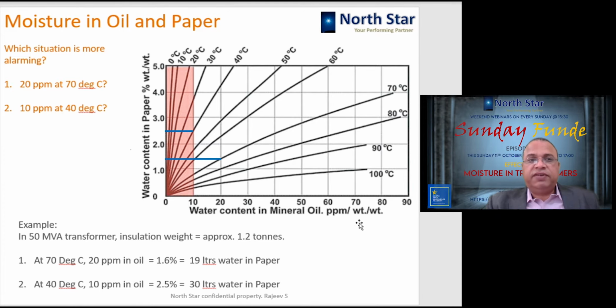So what does this graph tell us? Look at two situations. One sample is at 20 ppm and 70 degrees centigrade, meaning this transformer is operating at 70 degrees centigrade and the ppm found in it is around 20 ppm. The moisture content in this transformer is 1.5% in the paper. The other is 10 ppm, a low quantity, and the temperature is also low, 40 degrees centigrade. But if we look at this graph, though the ppm is less, the moisture content is around 2.5% in the paper. So this situation is more severe than the other.